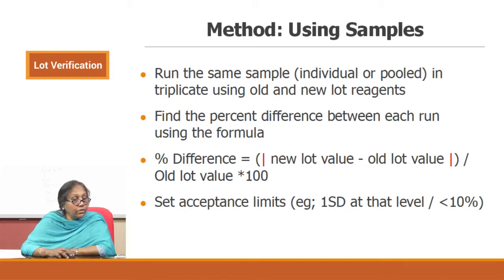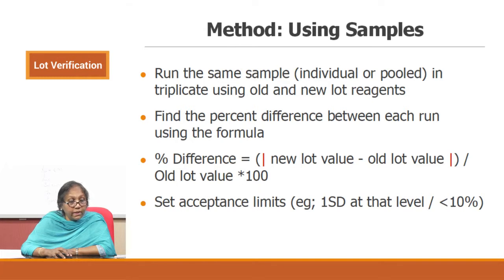Find the percentage difference between each of these using the formula: percentage difference equals the absolute value of (average of the new lot minus the old lot value), divided by the old lot value, multiplied by 100. Then you set your acceptance limits.